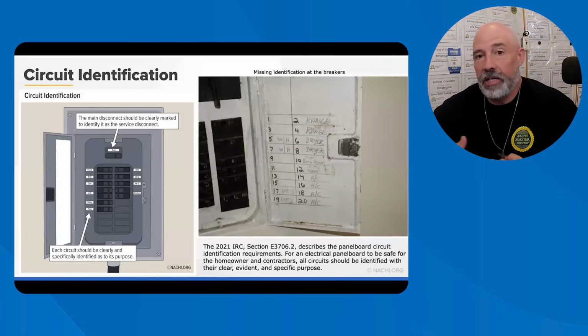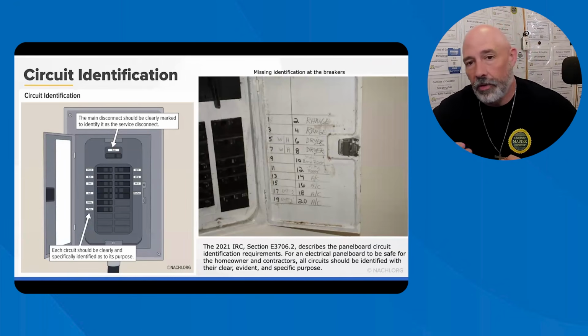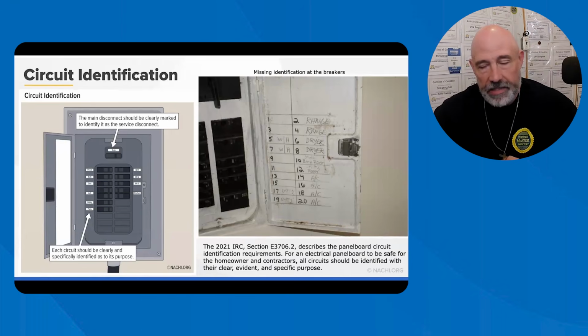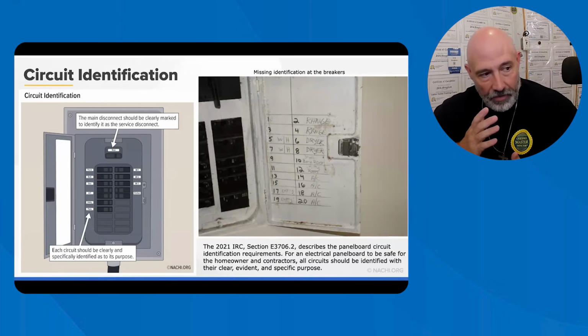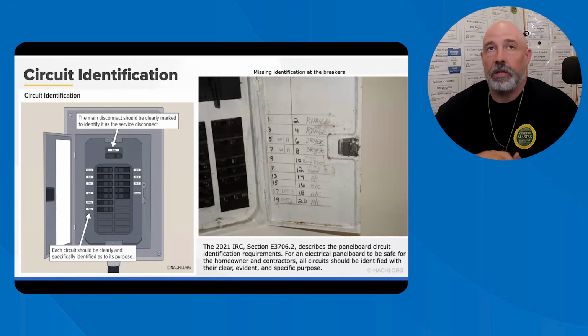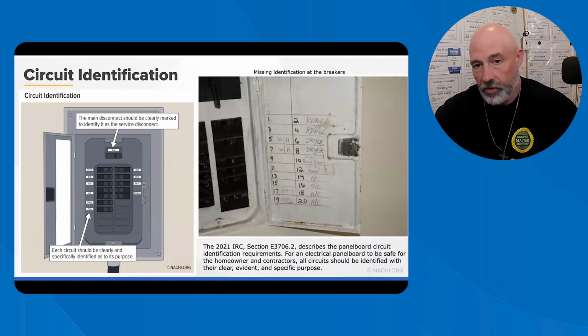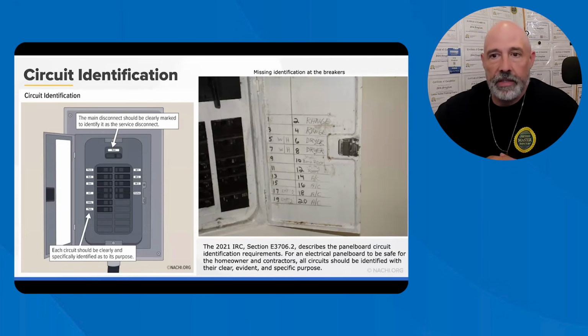So the other thing is that you want to make sure that things are labeled. Now, I don't expect anybody to go through and make sure that that is properly labeled. That takes a lot of time and effort. And for the most part, I look at it, make sure that it kind of fits what it's saying. Like microwaves should be on their own separate circuit, things like that. If I see a microwave, okay, I'm good, and kind of leave it at that. If there is a spare or unused breaker, you might want to put that in your report.